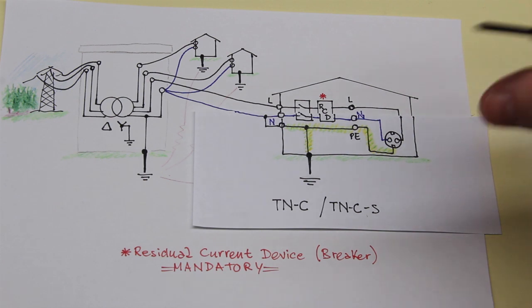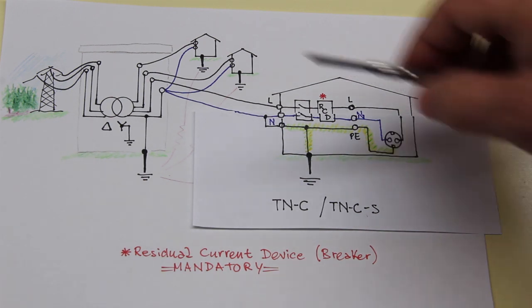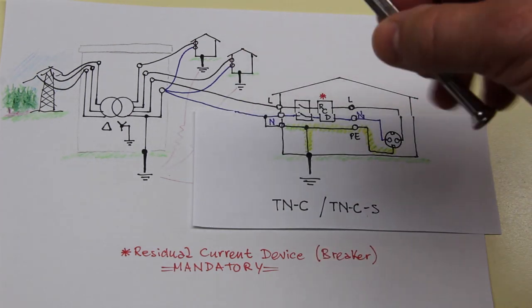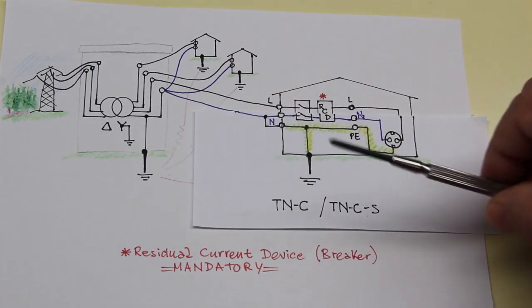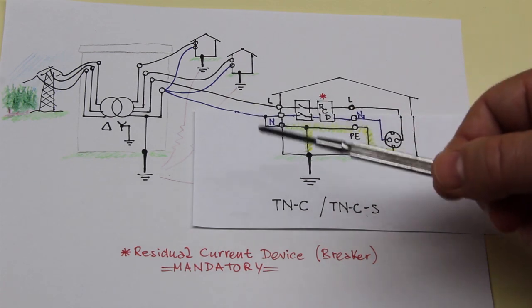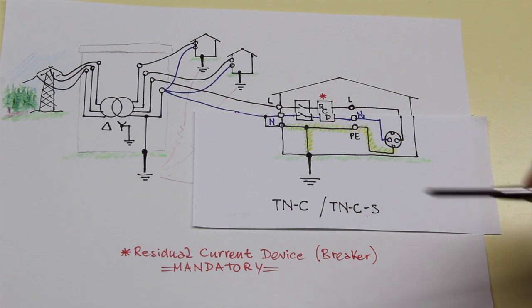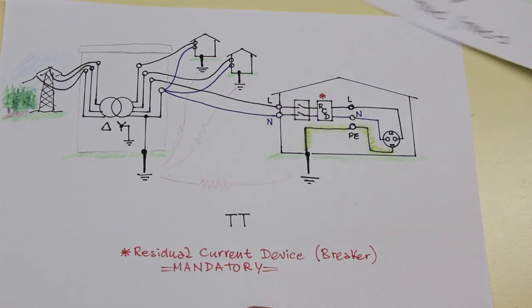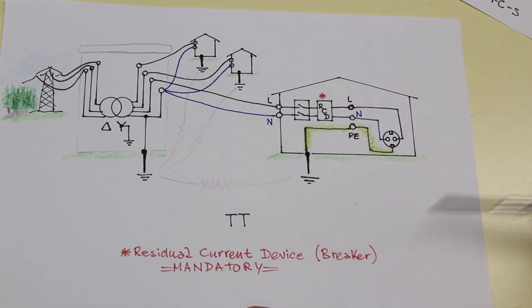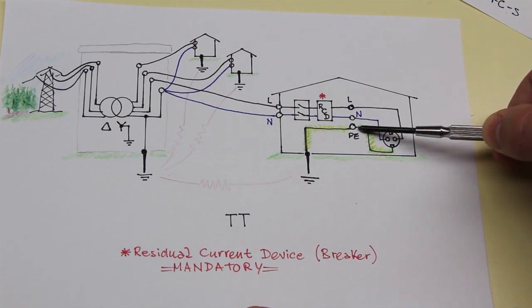What I'm discussing today here is specific to Europe or these earthing systems in North America, and not all North America, because for example there is the single wire system that has a different behavior. So what I'm going to discuss later is not applicable in those cases. That is important. So what is important to remember is the neutral in Europe and where there is a TT system, the neutral is never at the same potential of PE.